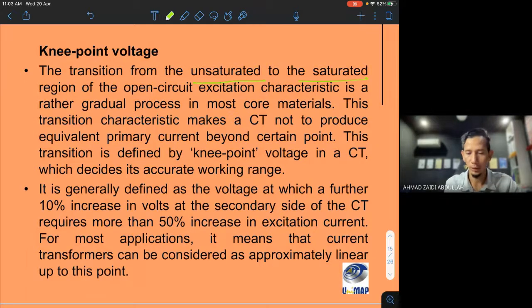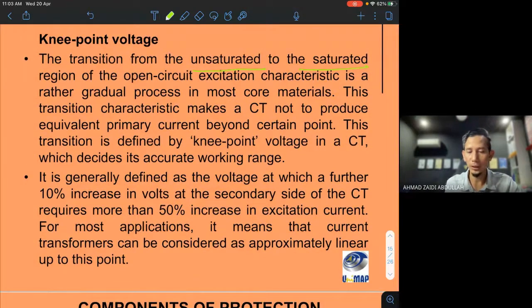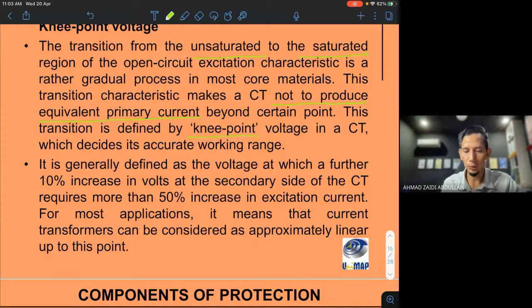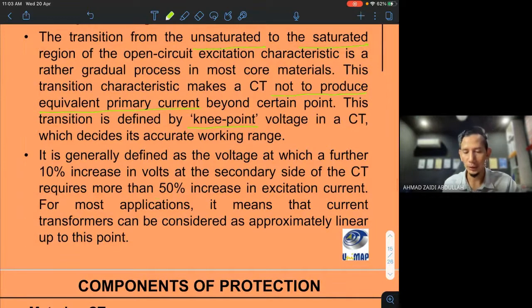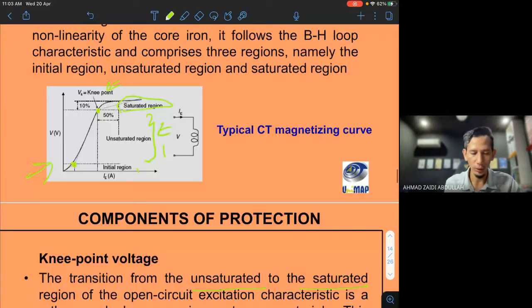This transition characteristic makes a CT not produce equivalent primary current beyond a certain point, so it does not produce any more. This transition is defined by the knee point. It is generally defined as the voltage at which a further 10% increase in voltage on the secondary side of the CT requires more than a 50% increase in excitation. Because this area from here to here is only up to 50% of the working area.